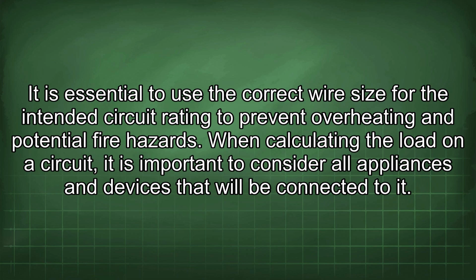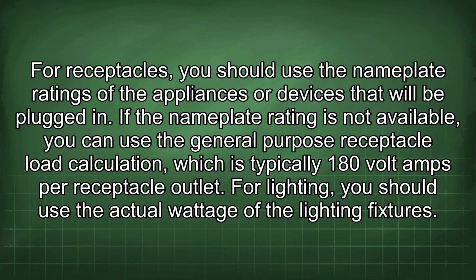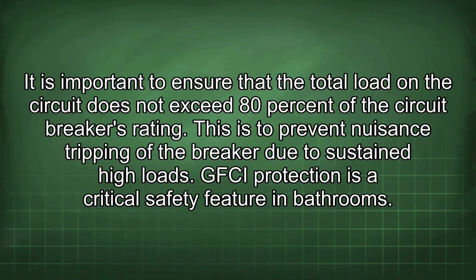When calculating the load on a circuit, it is important to consider all appliances and devices that will be connected to it. For receptacles, you should use the nameplate ratings of the appliances or devices that will be plugged in. If the nameplate rating is not available, you can use the general purpose receptacle load calculation, which is typically 180 volt-amps per receptacle outlet. For lighting, you should use the actual wattage of the lighting fixtures. It is important to ensure that the total load in the circuit does not exceed 80% of the circuit breaker's rating. This is to prevent nuisance tripping of the breaker due to sustained high loads.